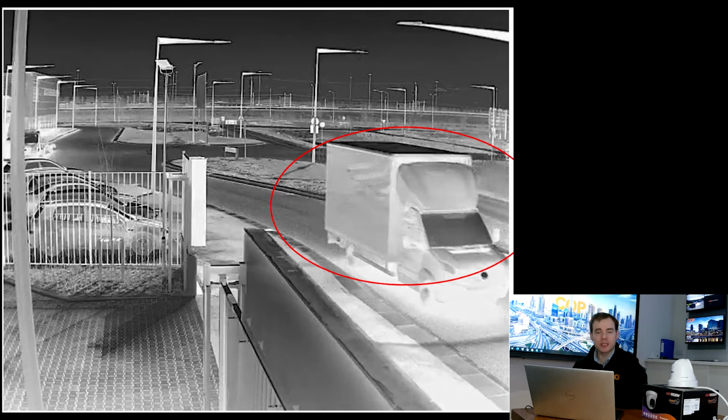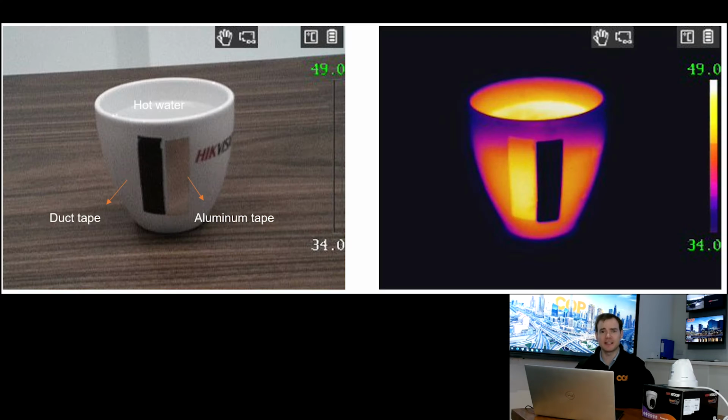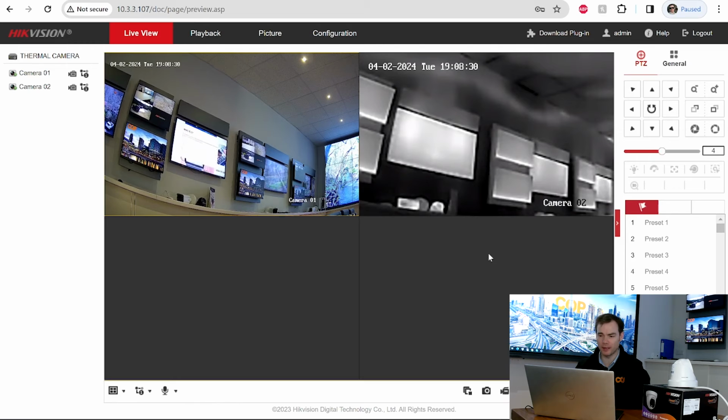Despite what Hollywood will tell you, thermal cannot penetrate through walls and glass and things like that. So it's seeing what's being emitted from the surface of that object. So if it's got a coarser, rougher surface, it'll usually have a higher emissivity rating, and you'll get a lot more accurate temperature reading. If it's got a smoother, flatter surface, it'll have a higher reflection rating, so it'll be reflecting the local environment and therefore not emitting what the true surface temperature of that device actually is. So do bear that one in mind.